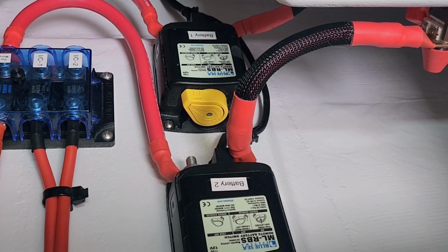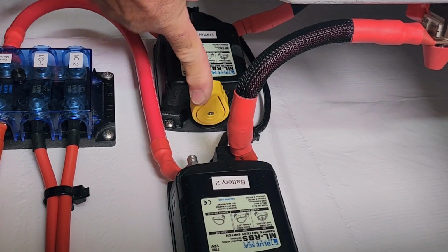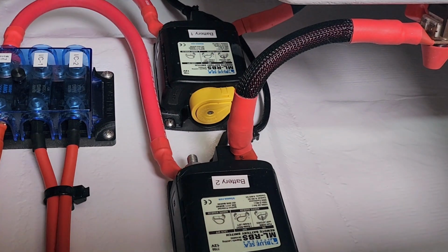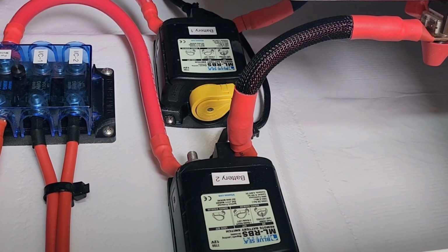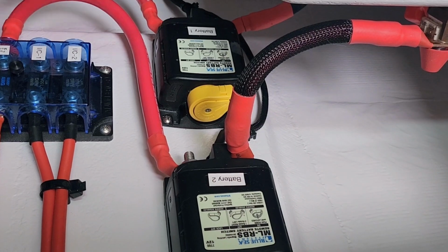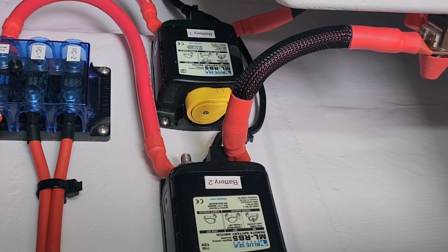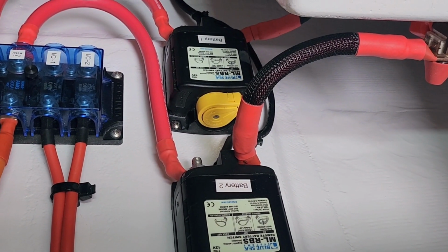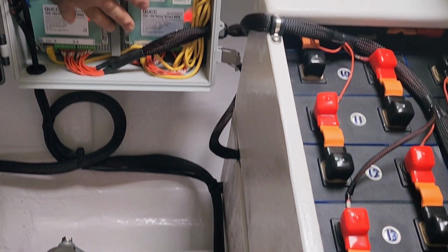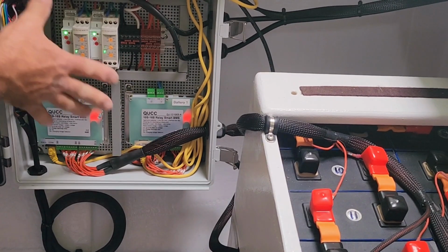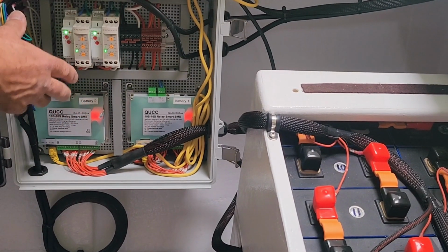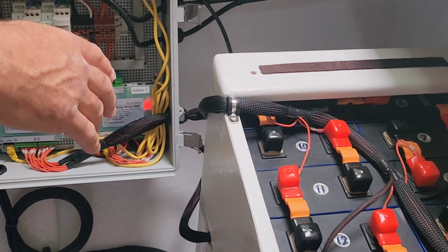When I'm ready to put the system back into service, I can turn it back on. I can either hit the switch back at the control panel to turn the relay back on, or I can manually turn it back on.